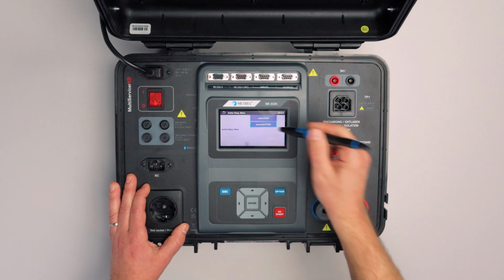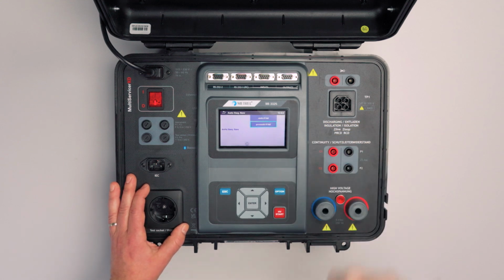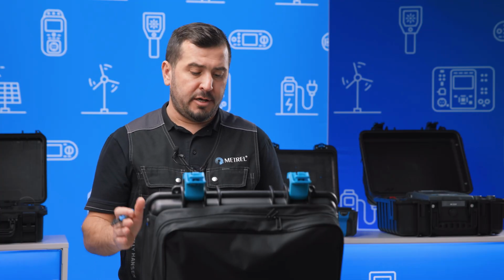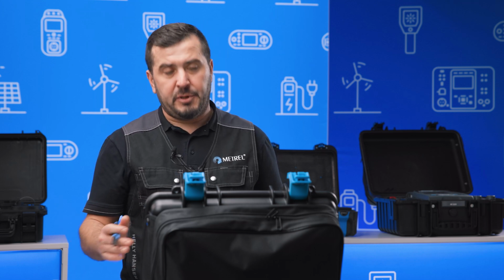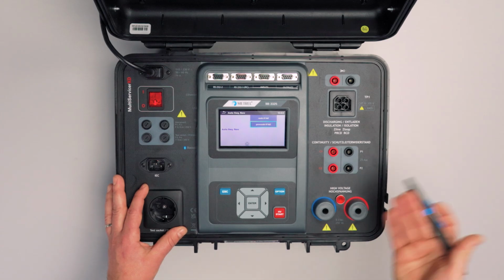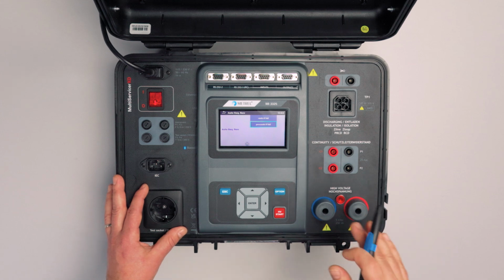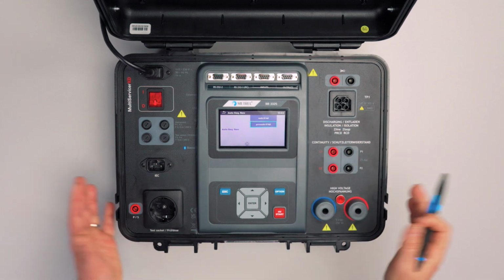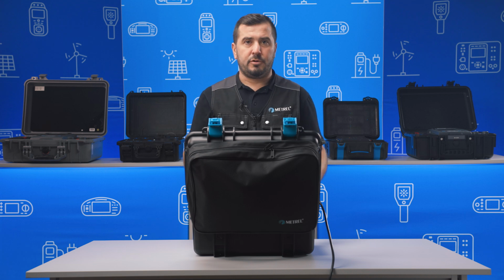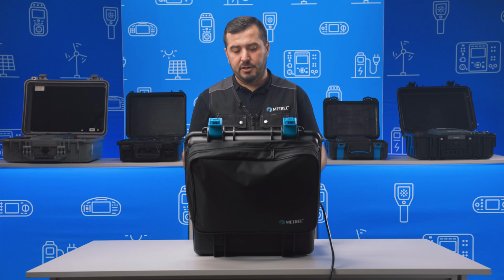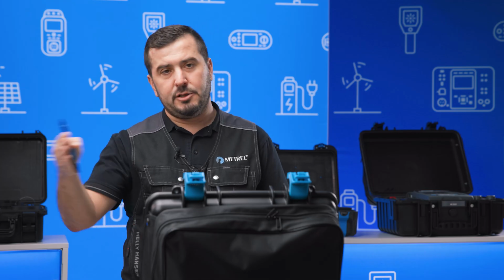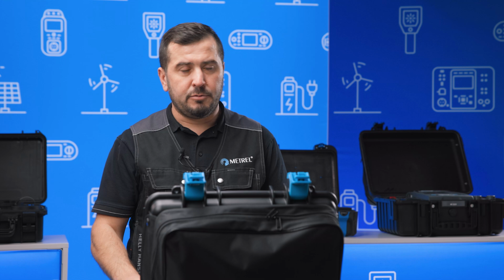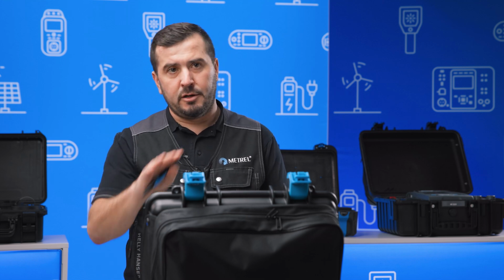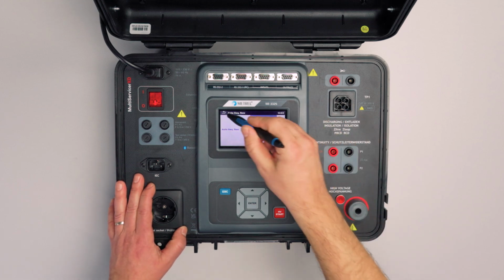Then the next option has effect on the auto sequence flow. So we have the option to choose end if fail or proceed if fail. This end if fail is typically used when testing electrical equipment, so appliances, periodically. So in case of the fail step, you will not be able to proceed with the test sequence, but it will be automatically finished. If we have the option proceed if fail, this is mainly for troubleshooting or testing on other equipment, meaning that even if we have some fail steps, we can still proceed with the testing, and after we finish, of course, appropriately label the parts that failed during the examination.